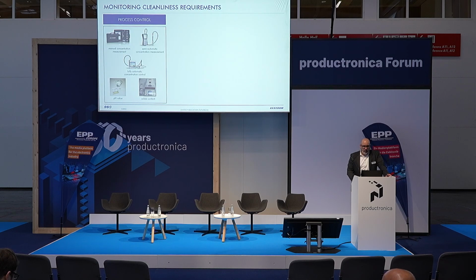Okay, so one last, or not the very last point, but one major last point is the monitoring of the processes, as I just mentioned. So how do you make sure that the process, once you have it validated and introduced in your production, is really working reliably? On the first hand, regarding analytics possibilities, we have the process control itself. So that means typically you have the cleaning medium, which has, for the water-based products, a concentration, which is the mix or the percentage of the cleaner in the water. So you need to control the concentration of the cleaner in the water. You also need to check pH values because this can change depending on the contaminations, and you need to measure solid contents also.